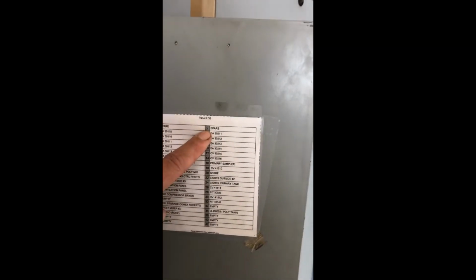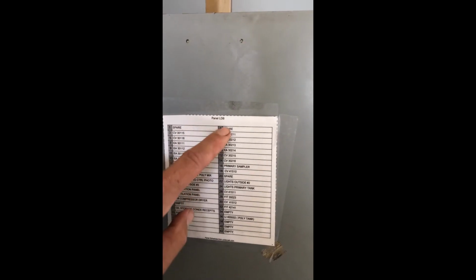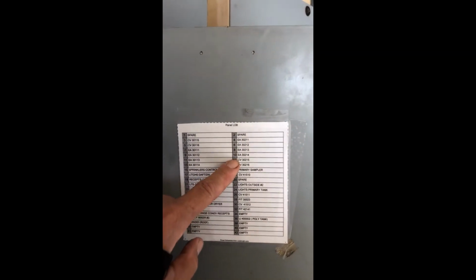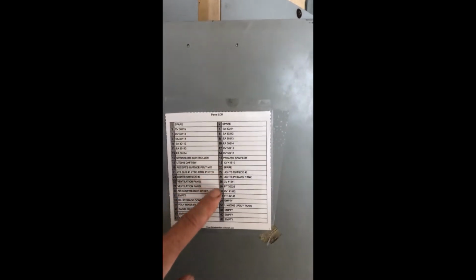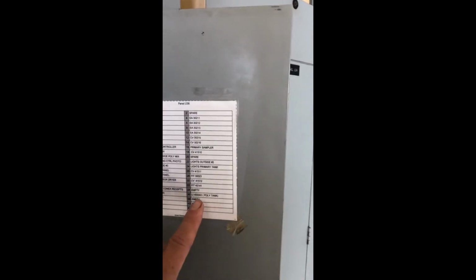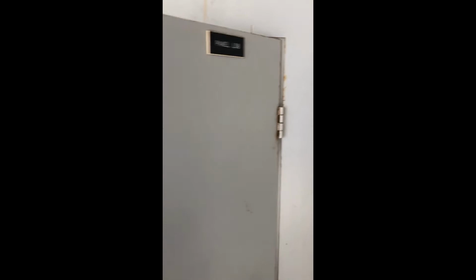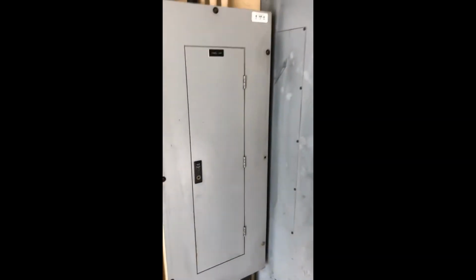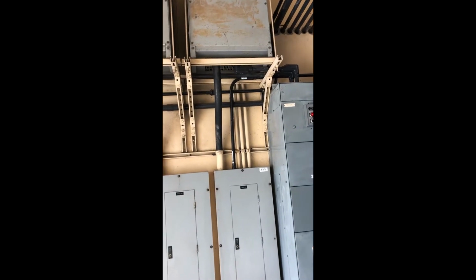These EA are actually supposed to be AE, and those are analytical. Those are powering some analytical instruments that we have here. Some pH meters and some stuff like that. Here's some more control valves. We got a sampler. Anyhow, we got a level sensor. But these are all loads that only require 120 volts. And above are the transformers that are reducing the voltage from 480 down to 208, and then bringing the neutral down, and then any of the legs 208 to neutral is 120.